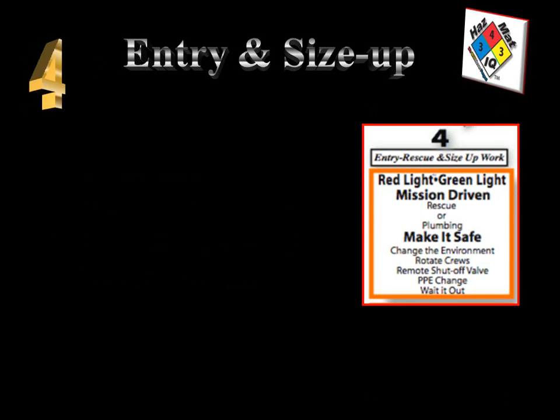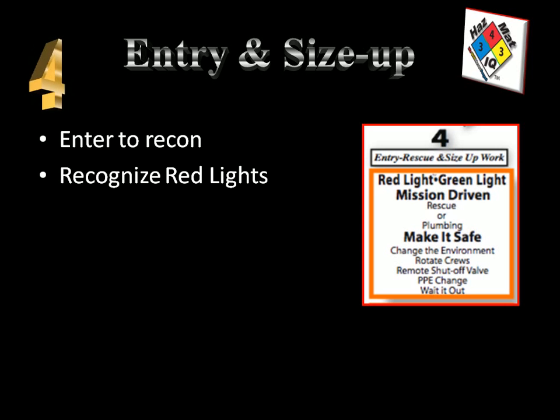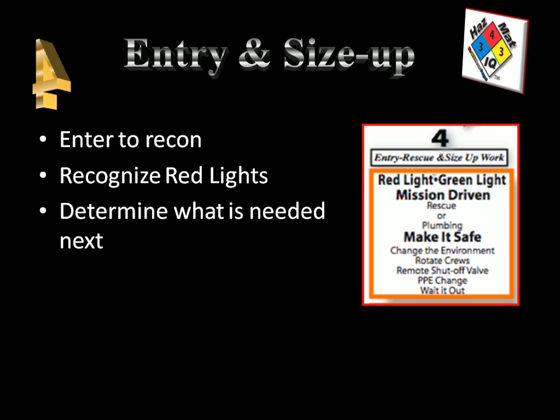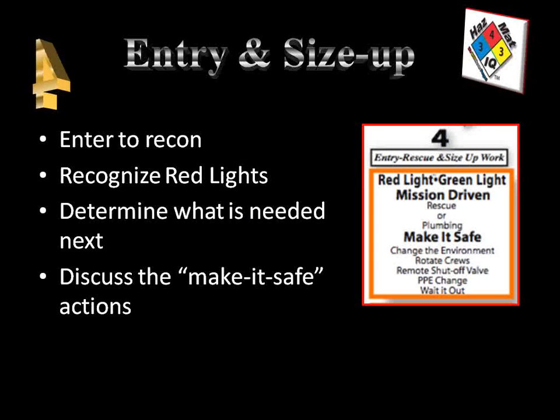Our final step is number four — the entry step and the size-up step for what work we need to do. We look at smart chart number 4 to guide us with the red light/green light information and how it's mission-driven. Our mission is to enter for reconnaissance, gather information, and make a determination on what type of work we'll have to do to take care of the product. Recognize your red lights and pay attention to data feedback from your instruments and know when to get out. For instance, with the CGI, anything greater than 10% means you should exit — that's a red light situation. Then determine what is needed next based on what we find from our original entry, and discuss the make-it-safe actions needed to make the incident scene safe and take care of the problem.